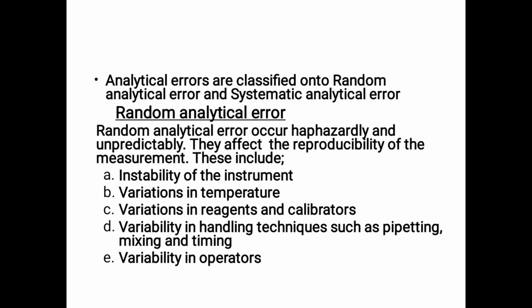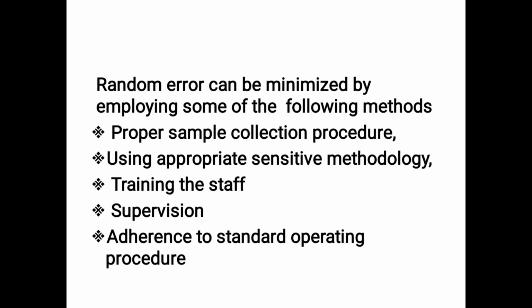So the reasons for random errors are instability of the instrument and variation in temperature. So we have to maintain the temperature. Usually they maintain a low temperature in automated instrument areas; the central AC is there. Variation in reagent and calibrator: if you are purchasing reagents from different companies, it may cause random error. Variability in handling techniques such as pipetting, mixing. Variability in operators: a sudden change to a new operator, a new technologist, may cause problems if untrained.